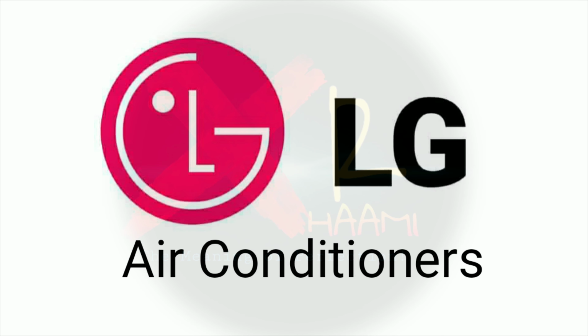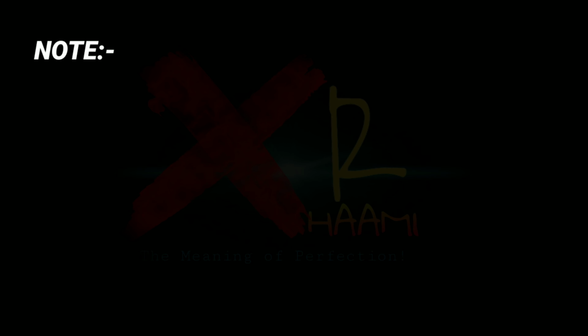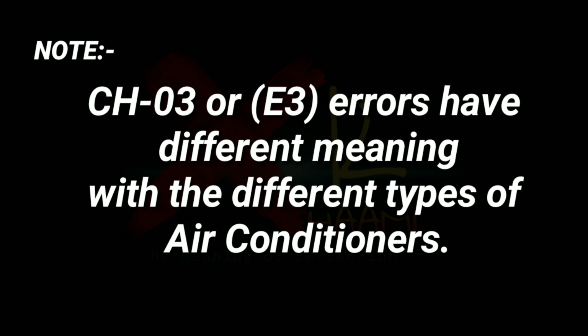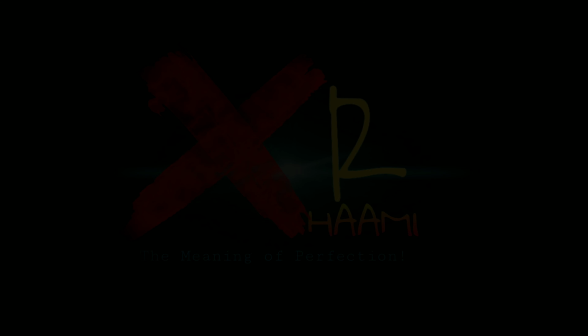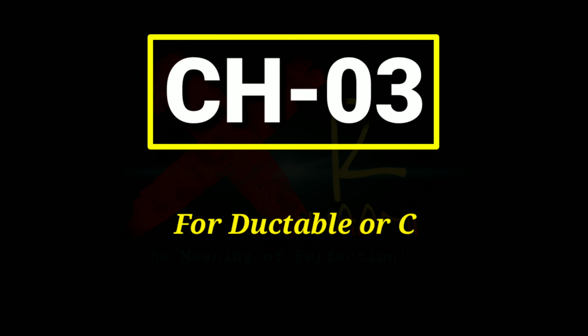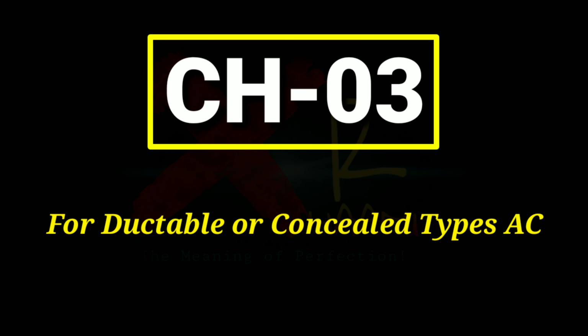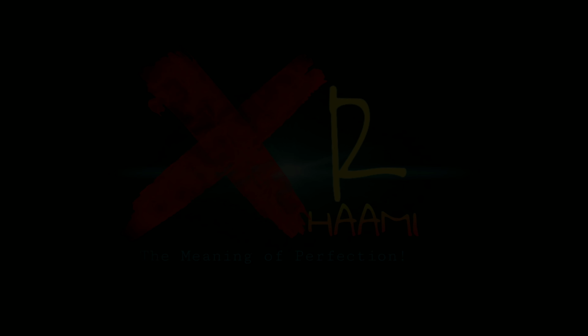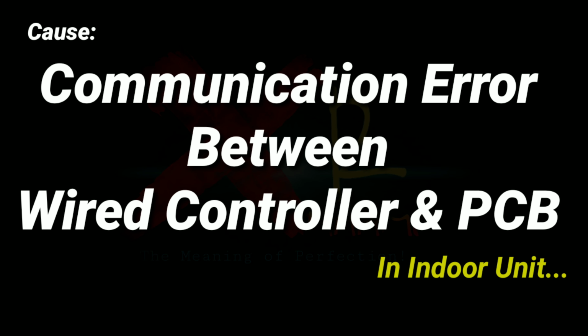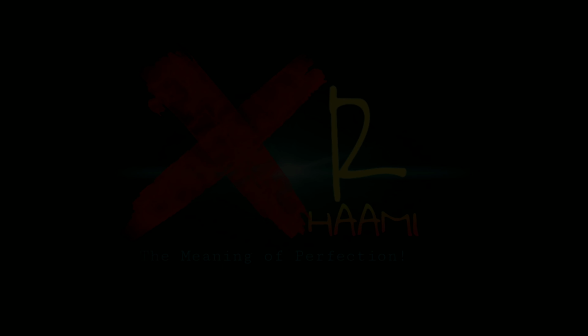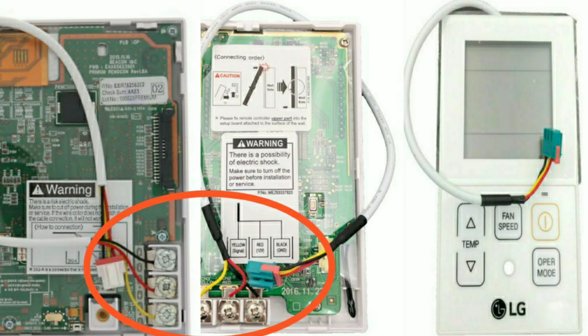Air conditioners. Note: CH03 or E3 error have different meaning with the different types of air conditioners. CH03 only for ductable or concealed types of air conditioners. The cause is communication error between wired controller and PCB. As you can see in the display, this is the remote control and the PCB and have wired.